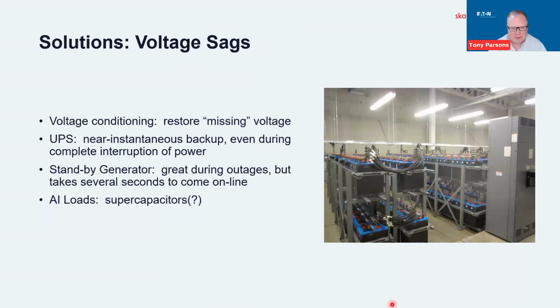For voltage sags, there could be voltage conditioning equipment that can help. There are different trade names there, sag fighters and sag ride through modules and things like this, that may be good for, for example, single phase voltage sags, but not as good for three phase, not as good for total interruptions. If you're trying to protect against a total loss of voltage, you may have to go to something like a UPS, uninterruptible power supply. The picture on the right-hand side shows an example of batteries backing up a UPS in a corporate data center here in the US.